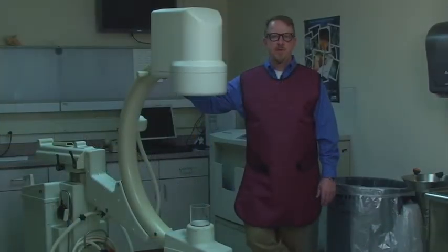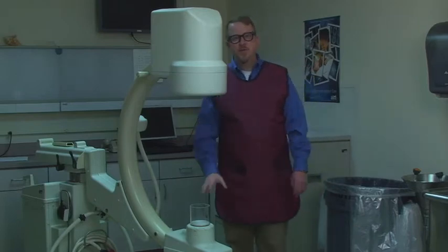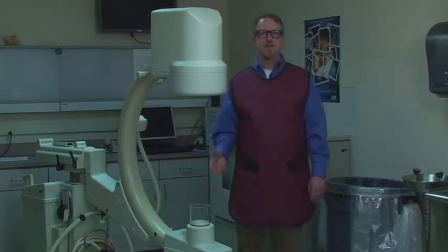The technologist should always use a mobile shield or wear a lead apron and extend the full length of the 6-foot cord on the exposure button to ensure the lowest occupational dose. Similar to a portable fluoroscopy machine, a mobile C-arm also is used in the OR. It is shaped like a C with the X-ray tube mounted on the bottom curve and the image intensifier or receptor on the top curve.